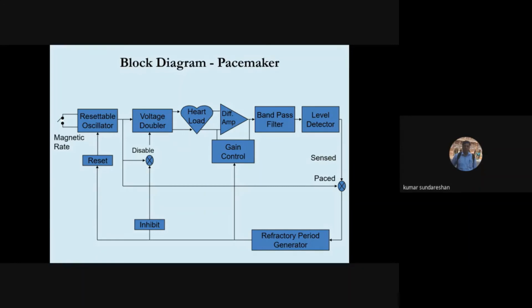But the most important part of the pacemaker is the oscillator. One has to understand the pacing pulses that have to be generated, and then how it is controlled, how that is actually being used in terms of logic to sense or to pace. So what are the various feedback mechanisms that go into this? So a lot of intelligence has to be enabled as far as the functioning of the pacemaker is concerned. So one has to understand all the basics of the functioning by looking at this block diagram.